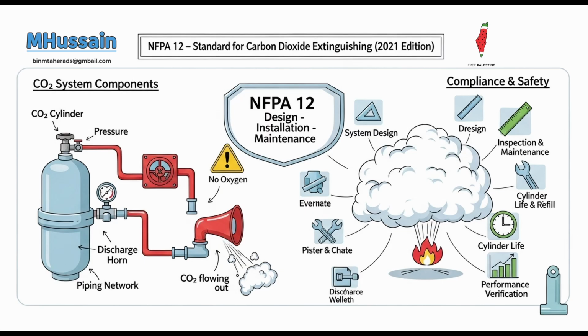Yes, one to control discharge from the CO2 storage cylinders, and a second to control discharge into the specific protected space. This dual valve system adds an extra layer of safety, requiring two distinct actions to release the agent. Two actions needed, less chance of mistakes. An exception exists for smaller systems, those with 300 pounds, 136 kilograms of CO2 storage or less, where only one valve is needed if the space is normally unoccupied and has horizontal egress. Small systems, unoccupied, easy exit, one valve.